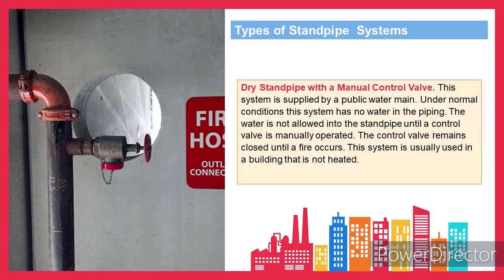Third type is the dry standpipe with a manual control valve. This system is supplied by a public water main. Under normal conditions this system has no water in the piping. The water is not allowed into the standpipe until a control valve is manually operated. The control valve remains closed until a fire occurs. This system is usually used in a building that is not heated.